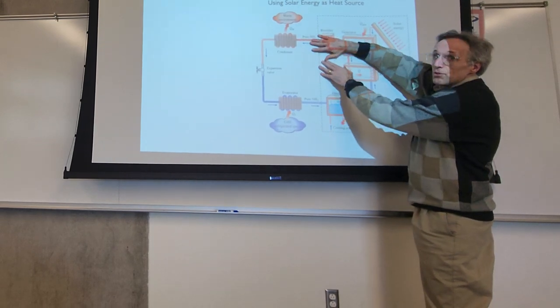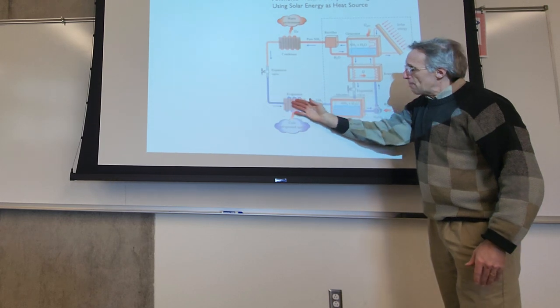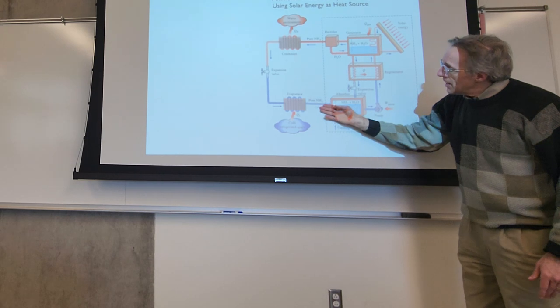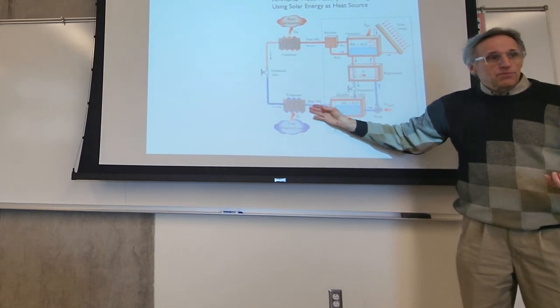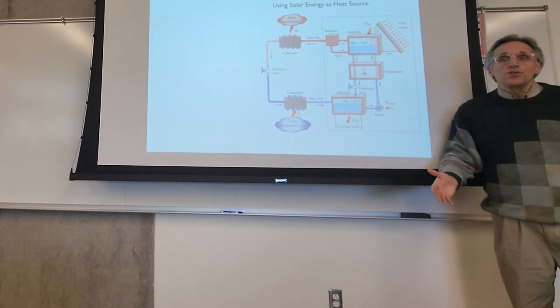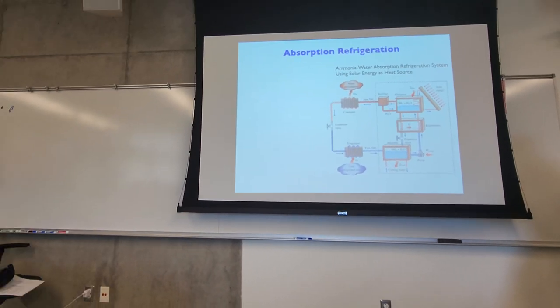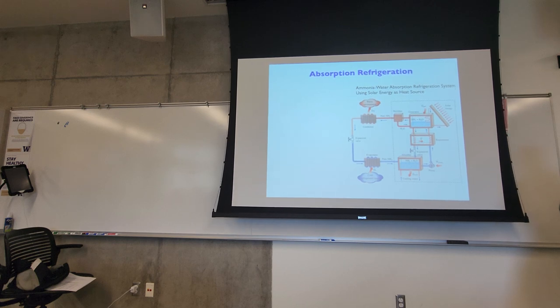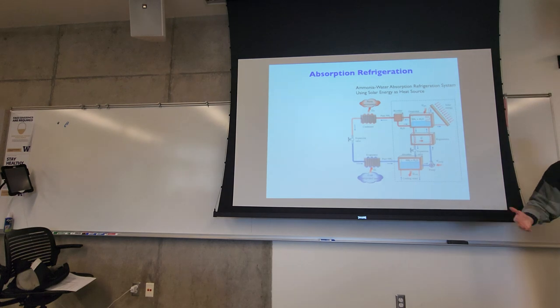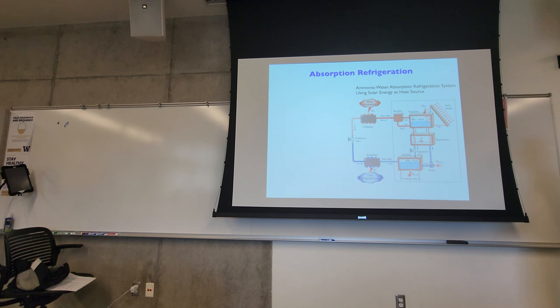As you can see, if you look at this part of the cycle, three-quarters of the cycle looks identical to vapor compression: the condenser, throttling, evaporator. But the difference is that when we get to the vapor state, in vapor compression we would compress the vapor. Now, as you know, compressing gas is energy intensive, because you're squeezing it like a balloon, and that takes a lot of energy. That energy use goes up dramatically when you get to very large flows, like in a big system, or a giant cold storage facility where you're storing frozen goods, food. The real reason you would use absorption is that you replace compression with pumping.